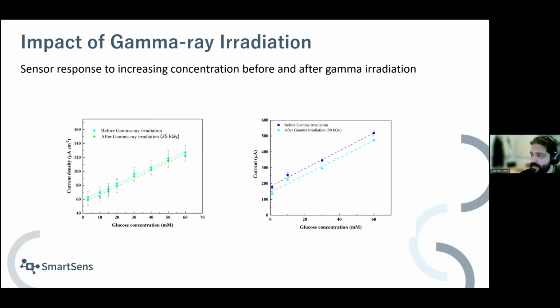Something about the sterilizations that we have investigated. This is with gamma radiation. The figure on the left is with 25 kilogray. So before sterilization and after sterilization with gamma radiation, you can see the slope of the calibration line doesn't change. Similar to the 50 kilogray on the right side. We have also tested steam sterilization. At the moment we can go up to 90 degrees steam, but after that, because of the coating materials we apply, the coating melts. It's not very useful at the moment. We are working on different coating material that can withstand temperatures up to 140 degrees. But we can for sure sterilize the sensor with gamma radiation.